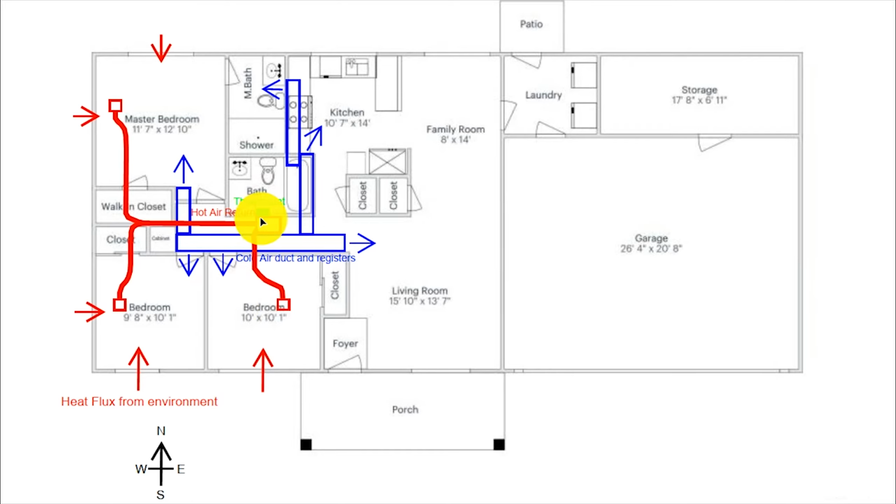So the flexi ducts running from the master bedroom and the southwest bedroom basically ended up being identical, with about 23 feet of the 25-foot run being used. The flexi duct going to the 10 by 10 bedroom was much shorter, about 12 feet or so. This would have been a bit of an issue because the 10 by 10 bedroom would have gotten a lot more hot air pulled out and cold air added to it than the other 2 bedrooms. So I actually throttled this louver down to about 50% open to compensate for that and even the flow out to the bedrooms.